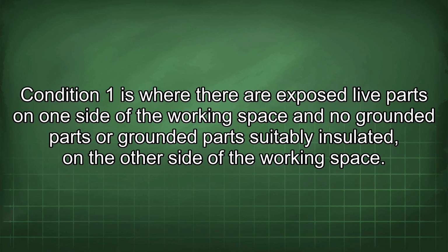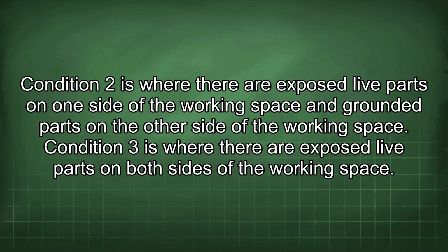Condition 1 is where there are exposed live parts on one side of the working space and no grounded parts, or grounded parts suitably insulated, on the other side of the working space. Condition 2 is where there are exposed live parts on one side of the working space and grounded parts on the other side of the working space. Condition 3 is where there are exposed live parts on both sides of the working space.